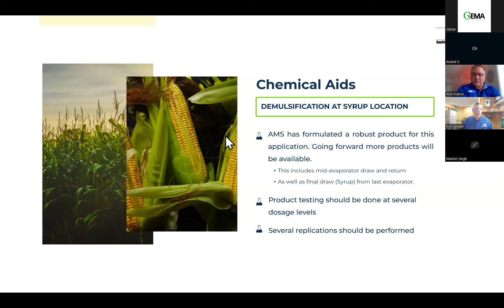By testing at different dosage levels, you get an indication as to where your dosage is going to wind up in the plant. That's not to say that it's going to equate 1-to-1 exactly. Bench testing seems to overpredict the dosage needed by a little bit. In other words, if your bench dosage says you need 200 parts per million, you may be at 180, 150 parts per million in application.